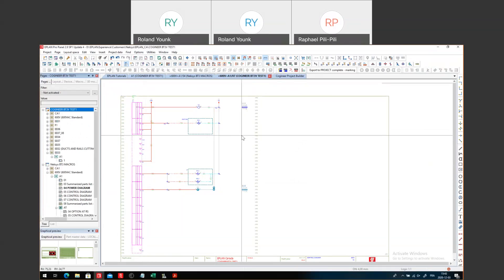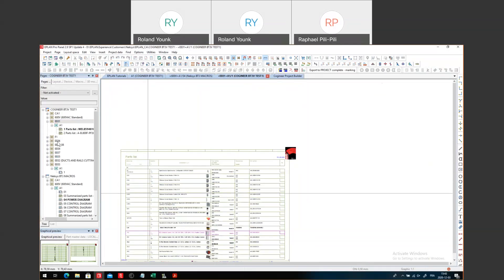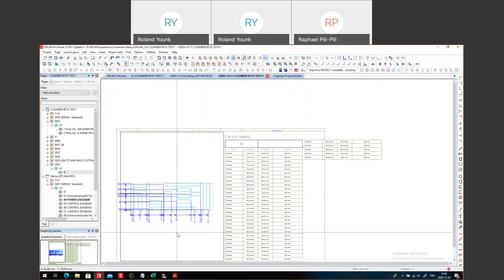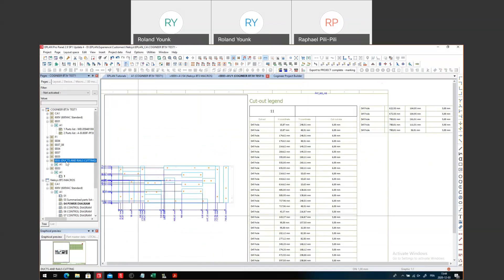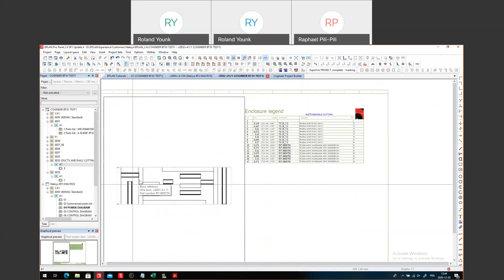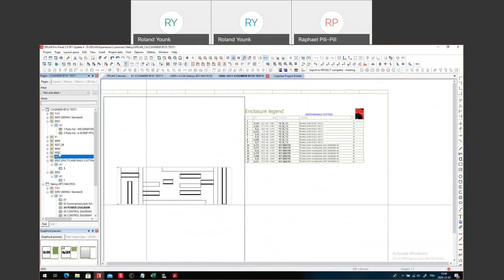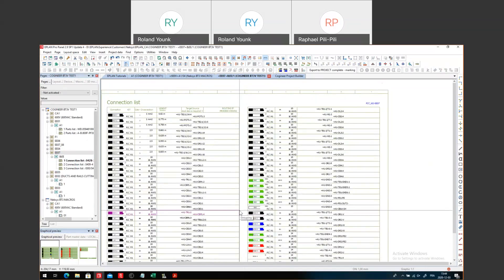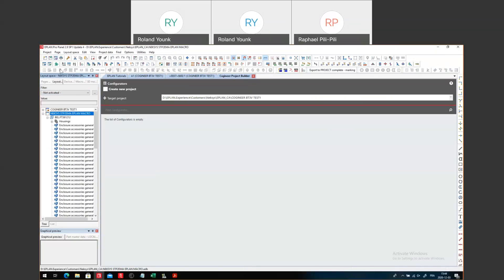That means my bill of materials, my wire list, my cable diagram, my terminal diagram — everything is generated in a single click. You can see it very quickly picks all the information within the schematics and generates starting with the first one, which is a kitting list. It also puts together all kinds of other things like a detailed production sheet for my different DIN rails — all the drill holes based on what we see. Another thing is the ducts in the rails and their lengths. I also have a detailed wire list, except I don't have any wire lengths at the moment because the components haven't been placed yet.